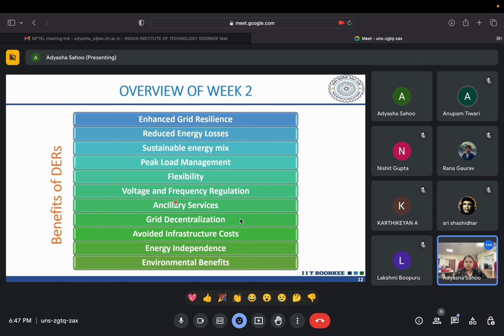No, that is different from the ancillary service. What you're talking about is, let's say, for operating that power you need offices or batteries — for running those systems. But ancillary service is different. This service is required by the power system in real time, so for a short period of time we have to take care of voltages and frequency, say within a 15-minute time window, to have this voltage support or frequency support. This type of service can be provided by the DERs.